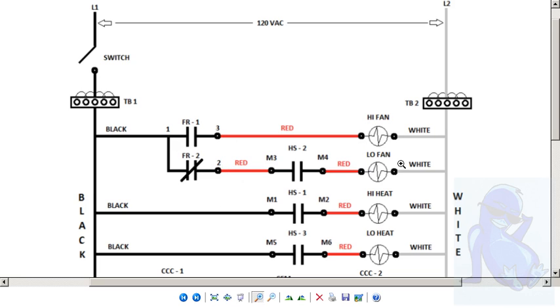Now this is probably going to be the same motor, but it's got 2 different speeds, or 3, or 4, whatever it requires, but it'll have a different speed. So we're just wiring it up to low speed, terminal 2, but before terminal 2 makes it to the fan, because that's connected, we have to run it through a sequencer that's open, and this is not going to turn on the low fan unless it calls for heat. When it does call for heat, this switch will close, and then the low fan will be able to operate.